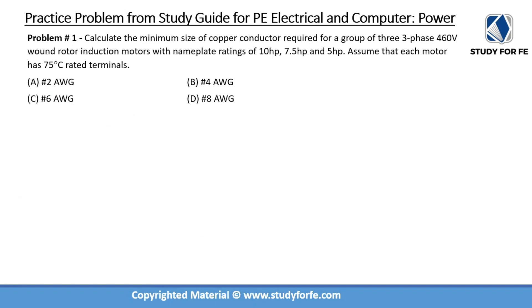Let us now work through some practice problems. This particular problem is from the study guide. It is asking us to calculate the minimum size of copper conductor required for a group of three three-phase 460V wound rotor induction motors with nameplate ratings of 10hp, 7.5hp, and 5hp.